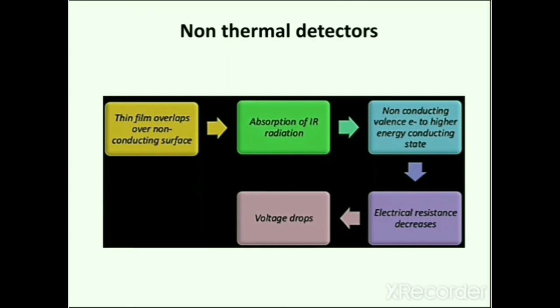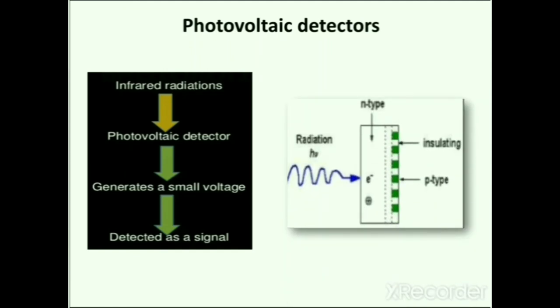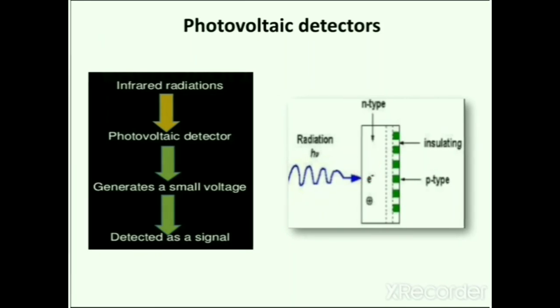The second type of detectors used in infrared spectrophotometers are non-thermal detectors. The response time and sensitivity of non-thermal or photonic detectors can be much higher, but usually these have to be cooled to cut thermal noise. The material in these are semiconductors with narrow band gaps. Incident IR photons can cause electronic excitations. In photoconductive detectors, the resistivity of the detector element is monitored. Photovoltaic detectors contain a P-N junction on which a photoelectric current appears upon illumination, generating a small voltage proportional to the incident electromagnetic radiation intensity.